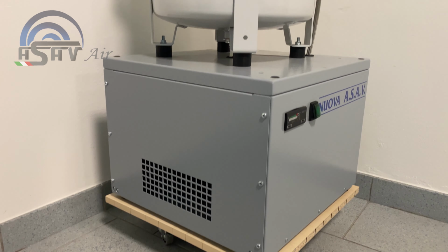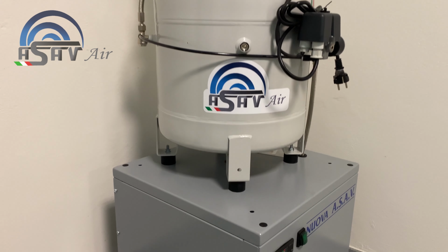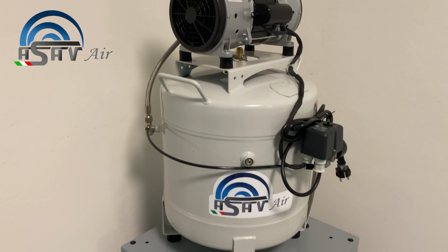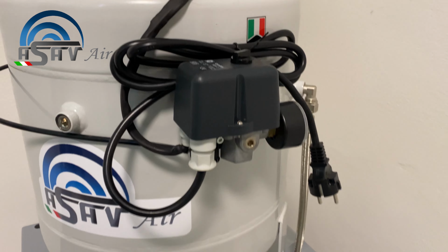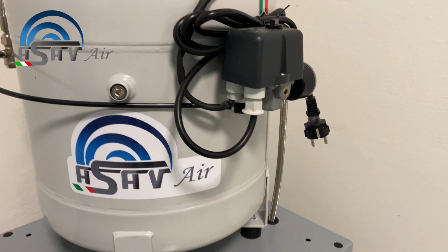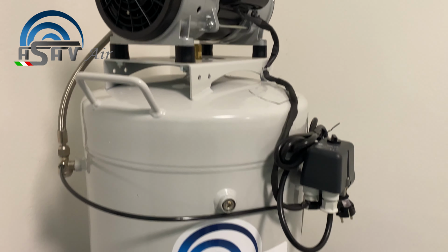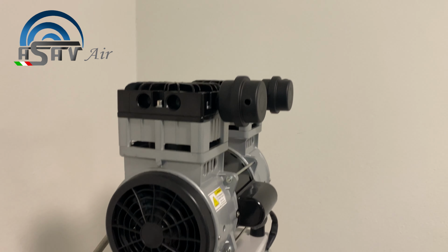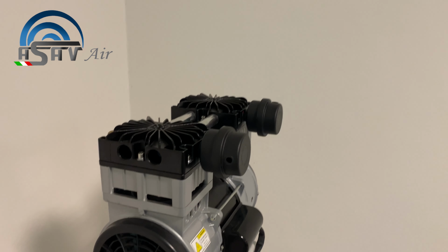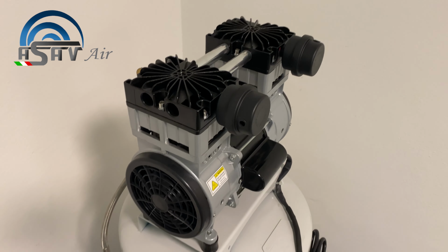The lubricating oil inside the compressor circulating is in contact with the pistons it lubricates, which compress the air we use. This mechanism creates vapors and aerosols in the air and leads to the pollution that will inevitably reach the patient. It is essential to save patients and keep the system perfectly functioning. Using oil-free compressors, you can guarantee efficiency and safety.